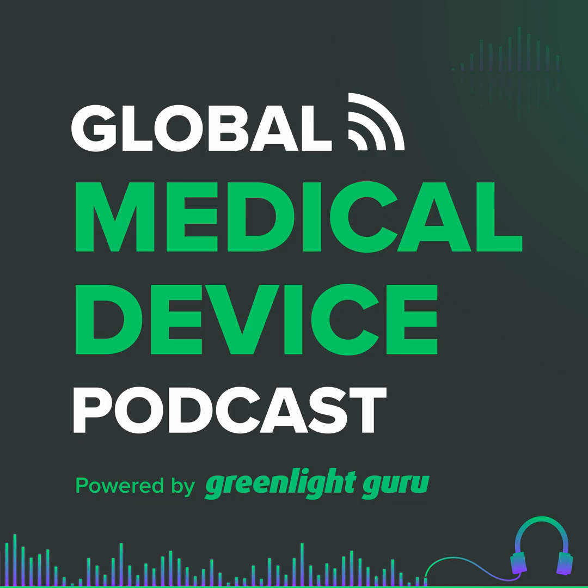Awesome. Yeah, I love that you use that as an example. I was actually talking to Mike Drews recently on another podcast episode about the common issues found in an FDA inspection that result in a Form 483. And if you look at the last 10 years, they're all the same. It's CAPA, design controls, and complaints. Within that design controls umbrella, which is almost tied with CAPA for first, a large percentage is tied to risk analysis, an inadequate risk analysis methodology.